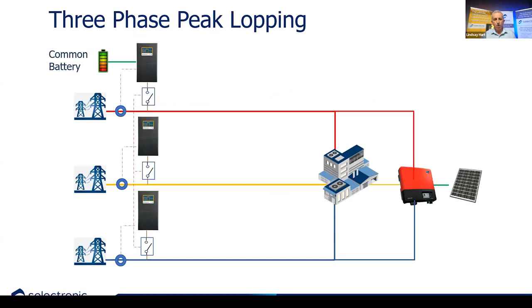So what we've got in front of you there is how we would go about this purely from a commercial three-phase peak lopping. So we've got our three-phase building in the middle there, which hopefully does look like some sort of commercial building. I think it does. And we've got some PV here. Whatever PV, we don't really care. But what about if we have to take control of our energy flow when the PV is not there? The PV, it may be at night, or it could be simply that we've got a very dull day and the PV's contribution is not sufficient.